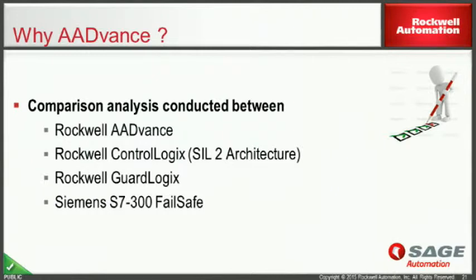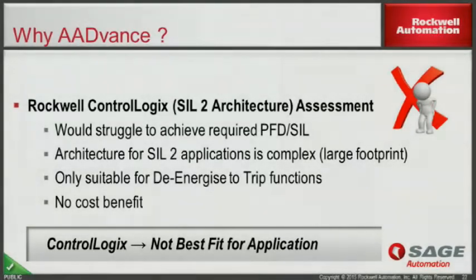Just giving you the Rockwell ControlLogix SIL2 architecture, Rockwell GuardLogix, and the Siemens S7-300 fail-safe systems. We found the Rockwell ControlLogix was not the best fit for the application because we would have struggled to achieve the high SIL2 requirements of this project. ControlLogix is suitable for SIL2 implementation, but when you take into account the safety inputs and the actuators with the logic solver, the resultant PFD would fall short of a high SIL2 system. The architecture for SIL2 applications within ControlLogix is quite complex, and that also equates to a large panel footprint.